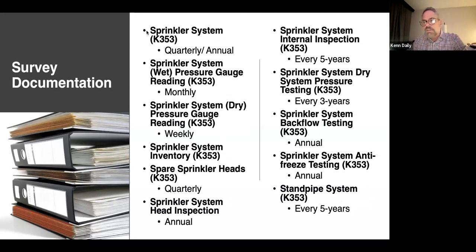This whole slide is on sprinkler. There's so much on sprinkler inspection, testing, and maintenance. As I said, it's the leading single citation in the country, K tag 353. As you see, every single one of these items on this slide, compliance goes back to K tag 353. So you have your sprinkler system, you have 4 quarterly inspections every 90 days. Somebody comes out from your contract company and inspects your system. Most of the 3 quarterlies are going to be mostly visual, and then 1 is going to be listed as an annual inspection, where it's going to be more functionally tested, the high flow water at that point, et cetera. But you have these 4 quarterlies.